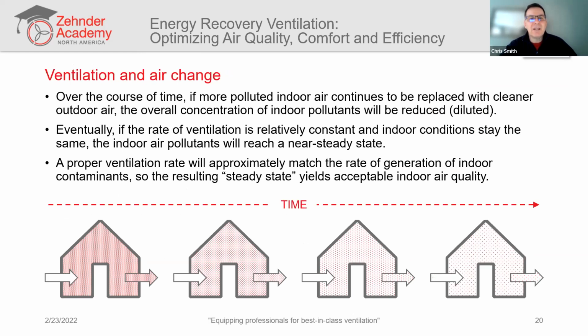So let's talk about ventilation and air change. We can establish an air change rate, and if we do that, we can match it to the building size. And over the course of time, the indoor air pollution will be replaced with cleaner outdoor air and will reduce the concentration of the pollutants. If the ventilation rate is pretty constant, then we'll reach a near steady state of indoor air quality contamination that's acceptable. So the proper ventilation rate, the rate we want of exchanging outdoor air with indoor air, is a rate that sort of matches the rate of the generation of the indoor air quality contaminants. And that's how we get to our steady state. And there are some suggestions in the industry for what those rates are.